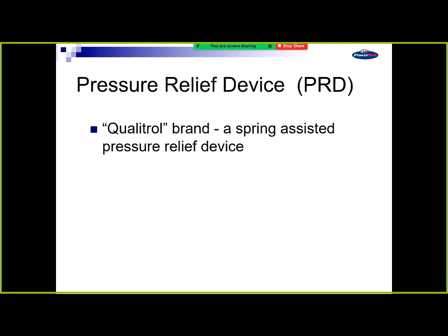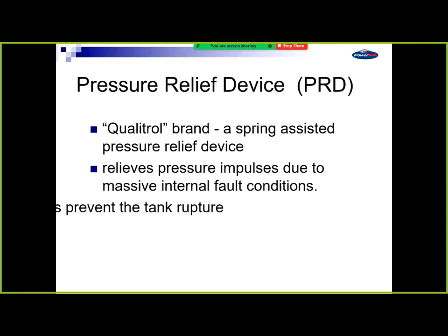Another one is a pressure relief device, which is often called a Qualitrol. But a Qualitrol is a brand name. It's just a spring-assisted pressure relief device. So when you get internal faults, like that oil surge I mentioned, there's also a lot of gas, there's a lot of internal pressure happening. You want to be able to release that. You don't want to rupture your tank. So there's a little device which has got a little hole. When a lot of pressure comes onto it, it opens, lets that pressure out.